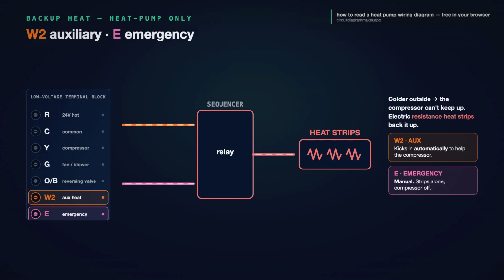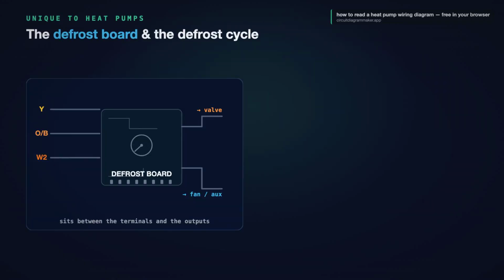W2 is auxiliary heat. It kicks in automatically to help the compressor when it is falling behind. E is emergency heat. You switch to it manually, and it runs the strips alone with the compressor off, useful if the compressor ever fails. Both energize a sequencer or a relay that switches the high current heat strips on. If you see W2 or E on the block, you're definitely reading a heat pump.